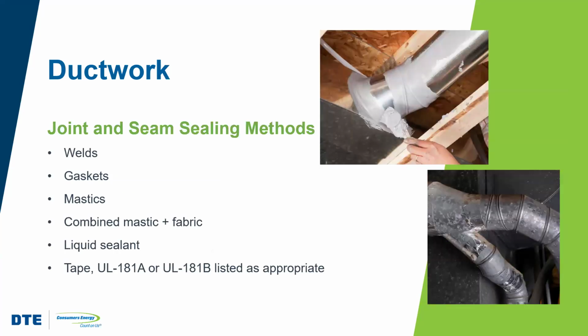And all the duct joints and seams, both transverse and longitudinal, will be sealed either by welding or with approved methods like mastics or liquid sealants or UL listed tapes. What won't be used to seal ducts is duct tape.